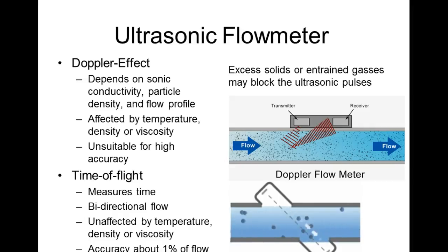So these guys are unsuitable for really, really accurate measurements. But they're real fast because you can get the heads that just mount together and you just strap them on. These time-of-flight ones have just about got to be put in there perfect. And it depends on the diameter of the pipe. So the spacing that you put, you'll see a lot if you look them up where they've actually got a measuring thing on it so you can measure out the placement.